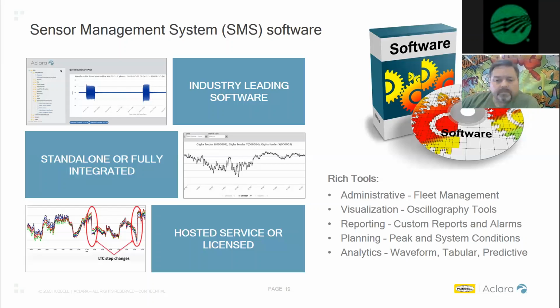When you're the user installing these sensors in the field, you have the ability to use our SMS interface, which is basically a map menu driven system that lets you control and manipulate where you place the sensors in our software package. We use a Google Map interface, so you'll have a Google Map view on your screen, and you can select the objects, which we call sensors, and place them on the feeder. We actually draw an electrical representation line from sensor to sensor, giving an idea of how that circuit is manipulated through your network, and that's all controlled by the user. So the hierarchy results in creating your own regions, substations, circuits, and sensor locations.